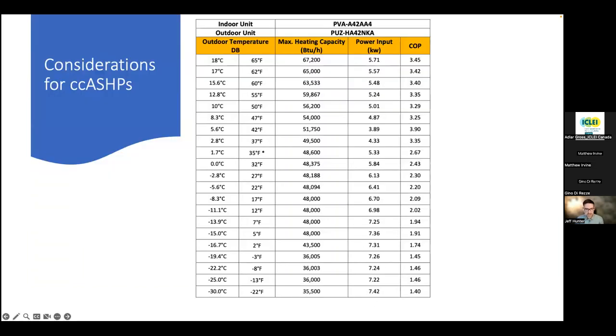And I can highlight that just to take a look here, an example of a manufacturer's data sheet. Now, I'm only showing the heating side of it, but you can get a feel for how the performance of the system changes over time. As the outdoor temperature drops, so too does the performance. So when I had 2.5 on this particular equipment, it would be right around 0 or 1 degrees Celsius. So perhaps it's not so much a problem for the individual consumer, because the consumer may get used to the fact that at a certain temperature, a backup system may need to turn on. They may not notice the difference between a 1.4 COP and a 1.7. But it does have a larger impact on the broader scale.